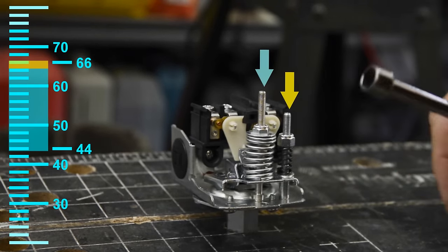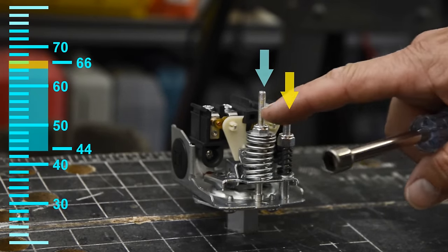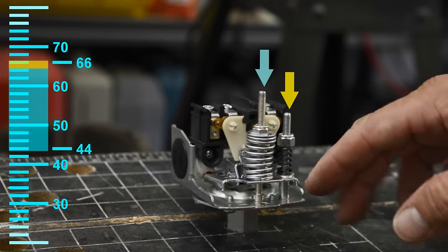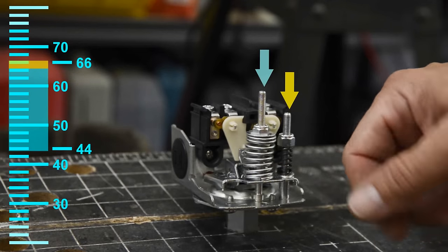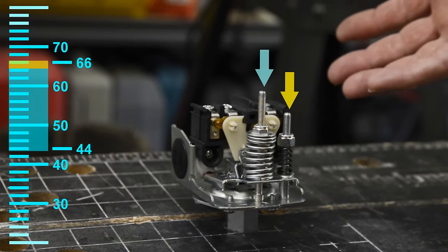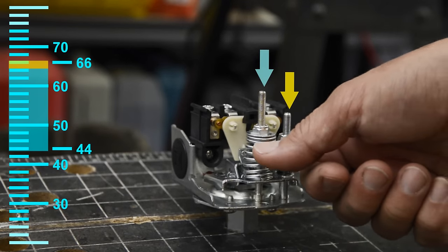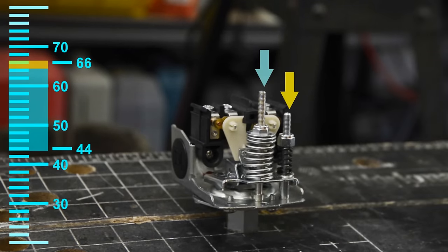And you would adjust this if your pump was cycling on and off a lot. This might have gone out of adjustment. The reasons it could go out of adjustment is because these are metal springs, and depending on the temperature and also the age of the pressure switch, they tend to change their value, and you would have to readjust the pressure switch.